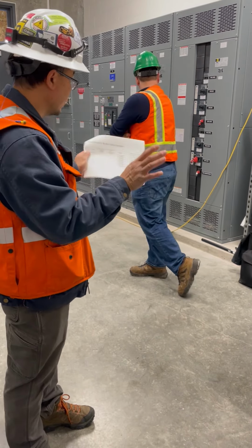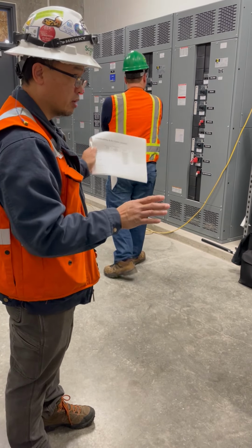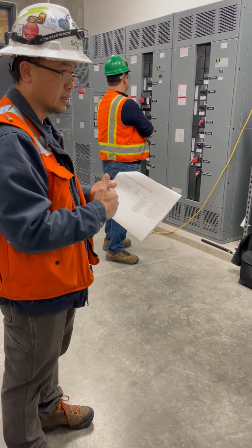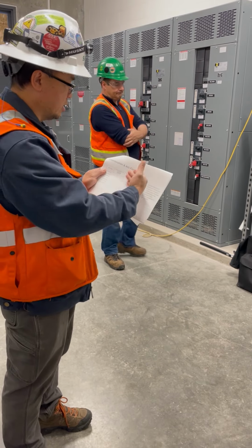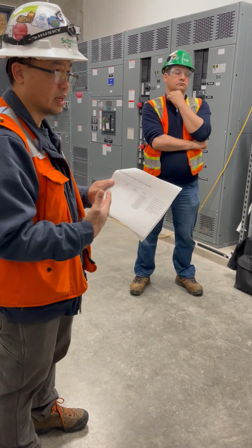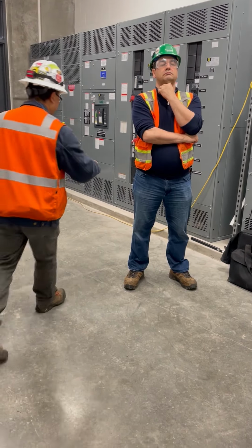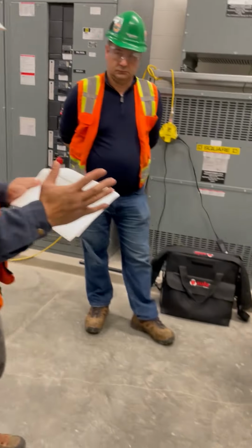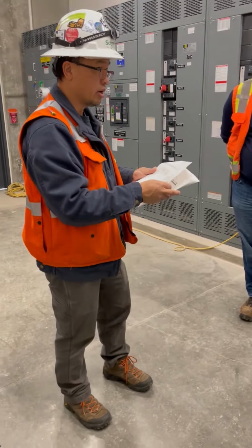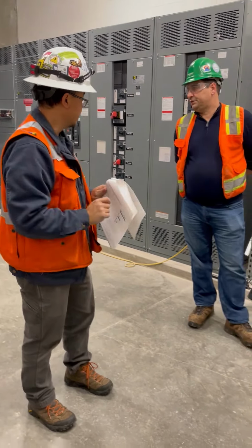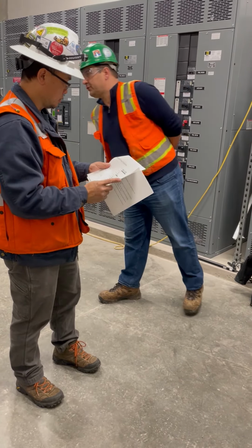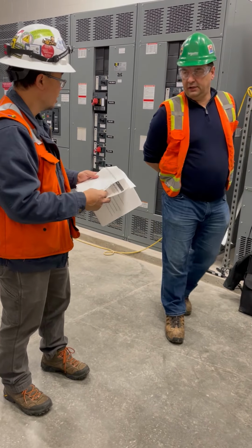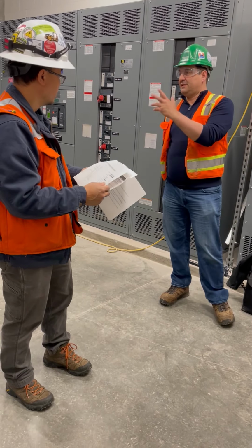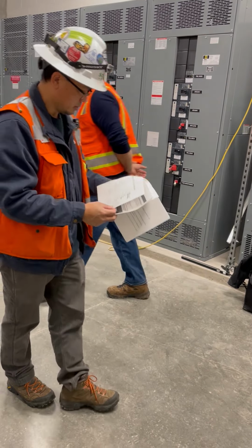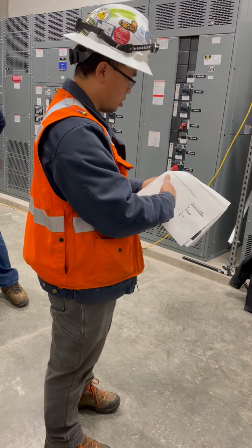Make sure you set the equipment's long time and short time pickup according to the study. Otherwise, these values are invalid. So you've got long time and short time pickup on all these right here, and you've got to make sure that it matches the study. Hopefully somebody came out here and dialed it in, right? I'm assuming they had Taurus do the startup and did all the settings, because I see the breakers pretty much set. Then if you look through the study, you'll see all this information.